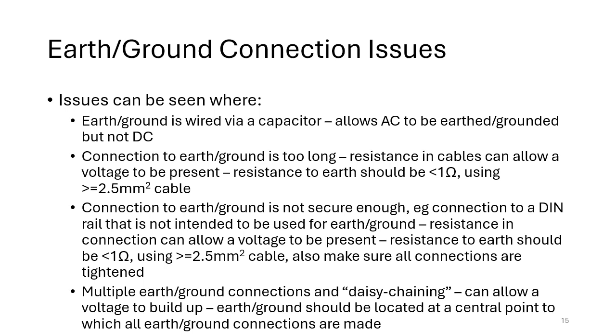Now it's also possible for the connection to the earth or ground to be too long, typically because the cable is too long. We think of cables as having no resistance, but they're made from copper or other metals, and they do have resistance, and you can also get resistance at the terminations themselves. So what you should make sure is that the resistance in cables should be low enough to prevent the formation of any sort of voltage. Ideally it's less than 1 ohm, and you also want to make sure that the cable is thick enough with a large cross-sectional area, and that will minimize the amount of resistance, and that will reduce the voltage. So typically, quite a large cross-sectional area, 2.5 millimeters squared or higher, and you need to make sure that the terminations are secure and they don't have their own resistance.